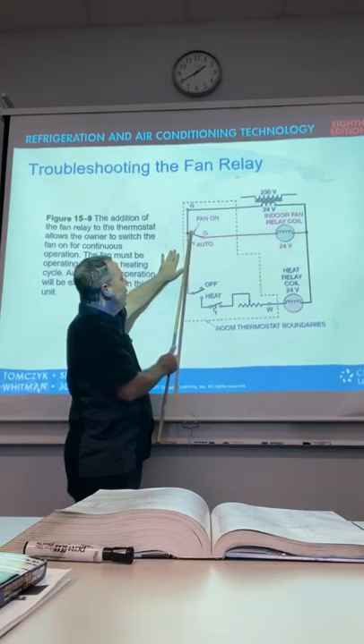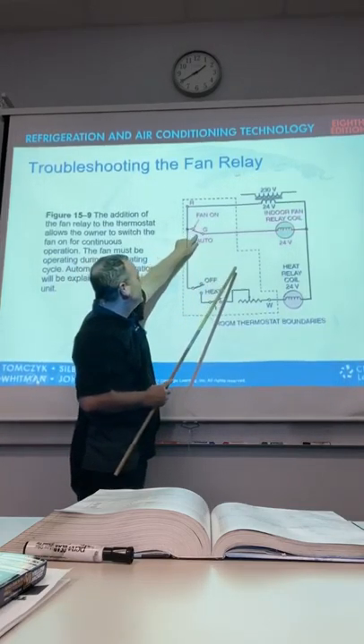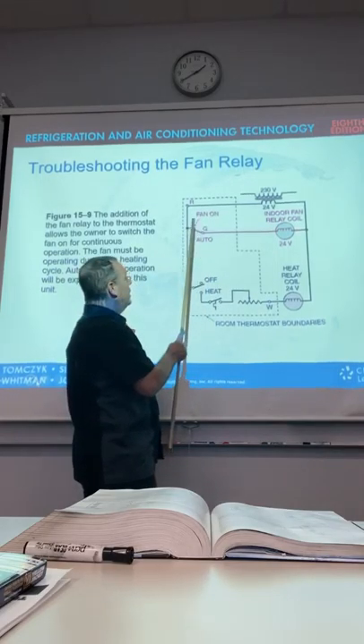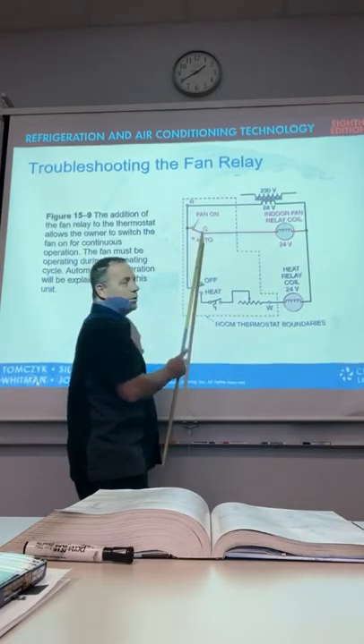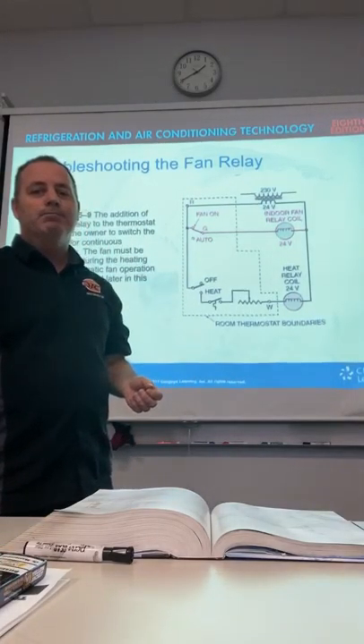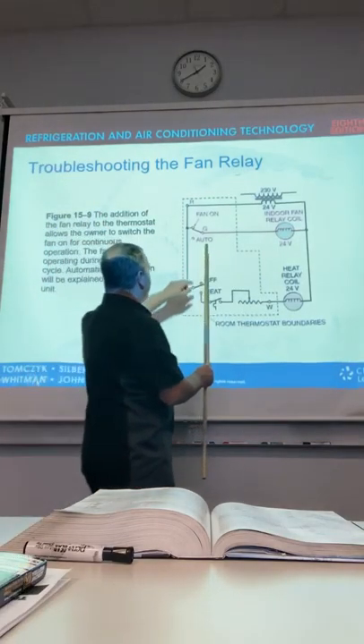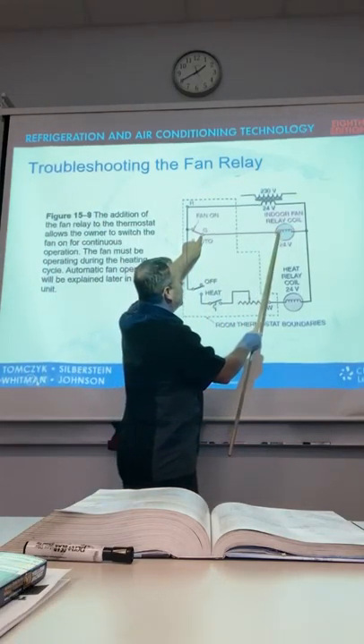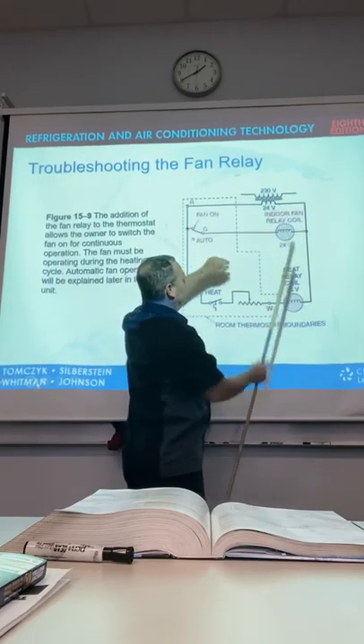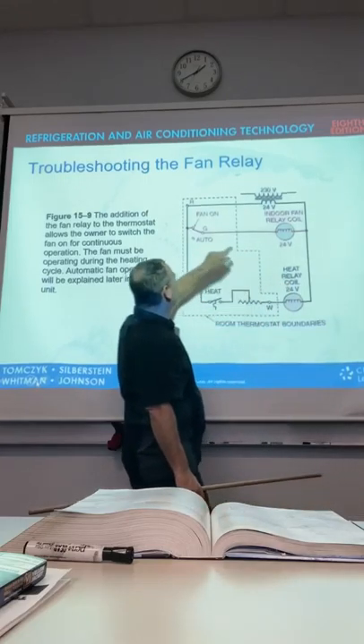notice it says fan on and auto. So, they take power and send it here, and when they have it on fan on, remember the last video, there's a path that's created where the power supply current will flow. So, now, the current's flowing to the terminal G. G is standard on a thermostat for fan, the blower, the indoor fan.